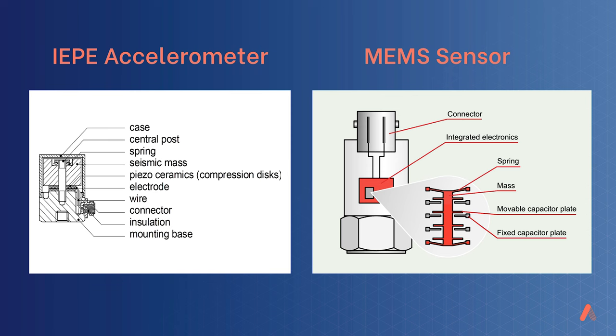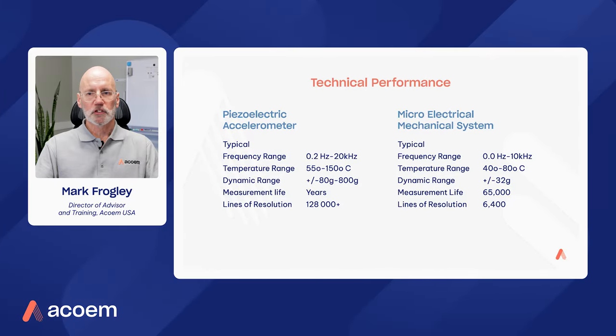On the left you'll see a piezoelectric sensor — an ICP accelerometer — and on the right, a typical construction of a MEMS sensor. The ICP accelerometer uses a piezoelectric crystal which, when depressed, creates a small charge measurable as vibration. That changing charge is measured as vibration, typically coupled with some sort of electrical transmitter to get the signal back to the data collection device. MEMS sensors use a different technology — capacitive discharge — measuring the change in capacitive distance between the mechanical pieces. Both work well, but they have different capabilities.